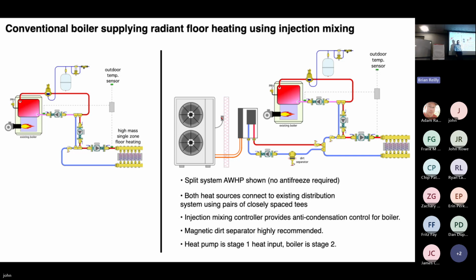And just to mix things up as far as the heat pump, I'm showing a split system, a DX refrigerant split system. So this would be a refrigerant tube here. This would not have to have antifreeze. You still could put antifreeze in if you want, but it doesn't require it because there's no water coming out to the heat pump. So it's, again, a minimally invasive way to tap the new heat source into the existing piping. And again, you'll see the heat pump is tapped in upstream of the boiler, and we've left as much of the existing piping in place as possible.